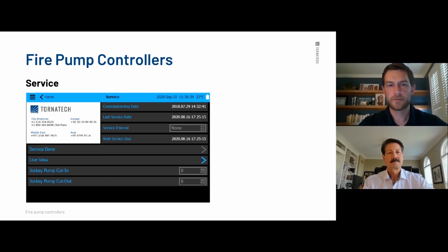Also, this is where I mentioned before, you can set the jockey pump cut in and cut out. So this helps us with statistics, with keeping track of starts and stops. It really does tell a lot about a system if your jockey is constantly coming on or going off, or if you have an issue with the main panel coming on and the jockey is not. It's a good spot where you can keep track of what's going on inside the system. So this does not actually control the jockey panel in any way. It's not telling it when to come in or go off, but if you put the cut in and cut out in here, it just gives us more accurate data.